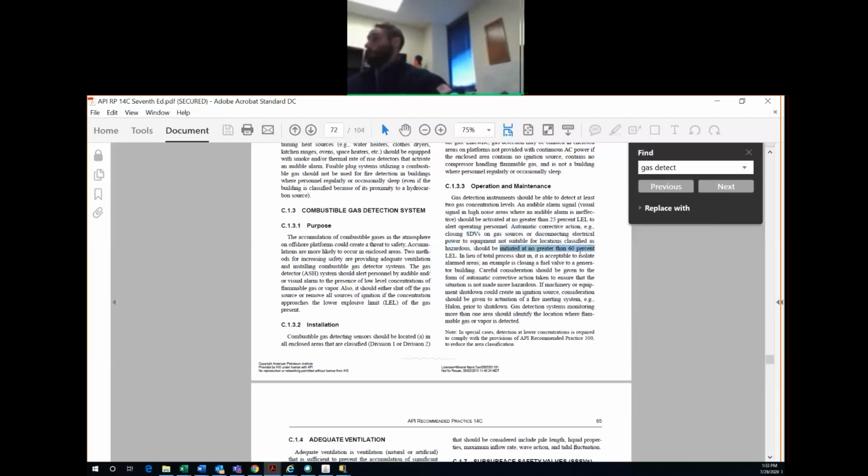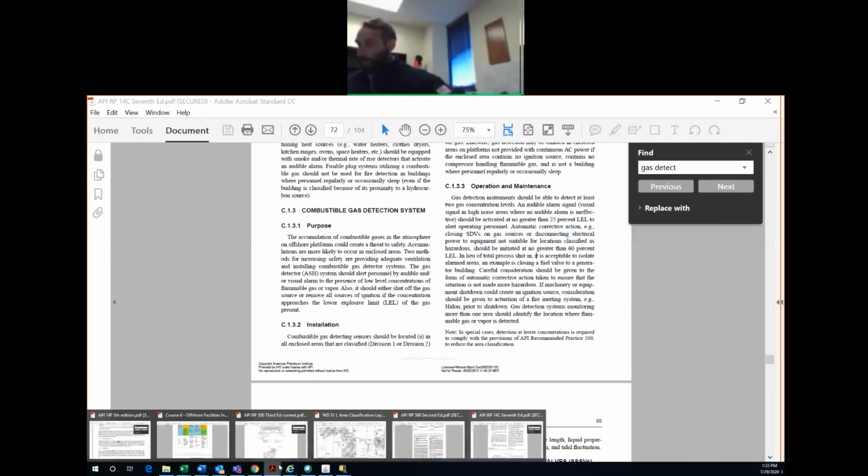And when do you do that? You do that at 60% LEL. So keep that number in your head, 60% LEL, and note how interesting it is that you'd be disconnecting electrical power to equipment that is not suitable for those locations. Okay. Put that in the back of your head, and then API 500.